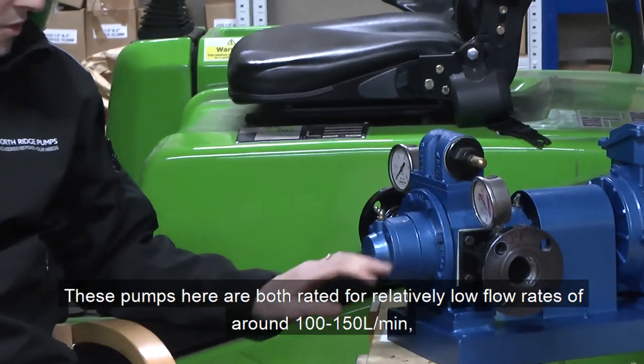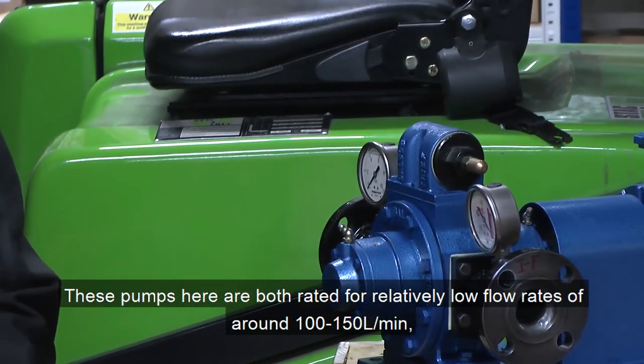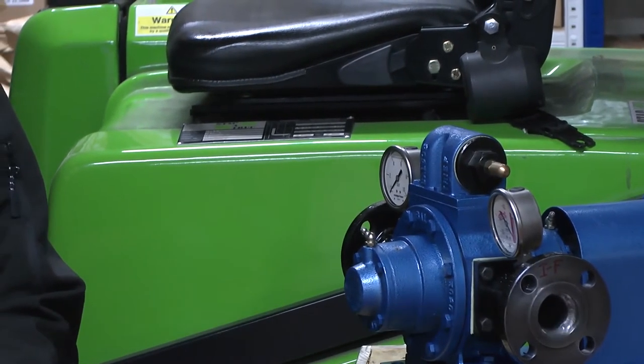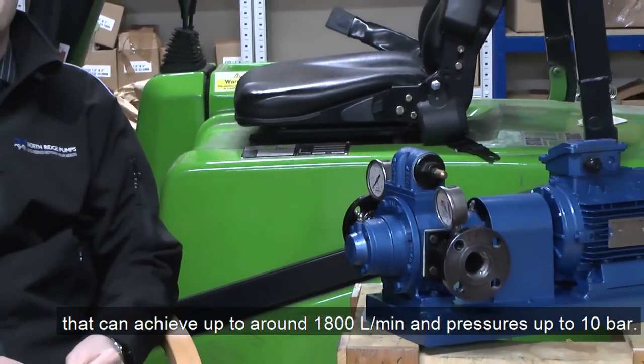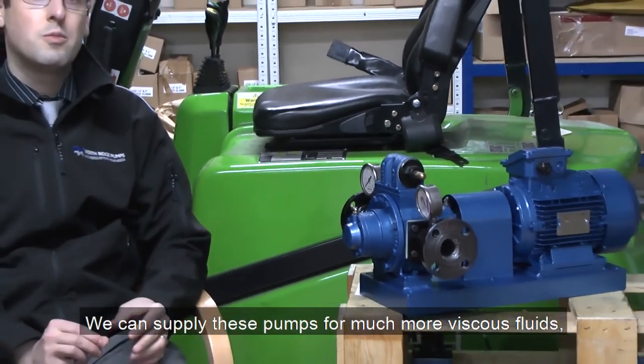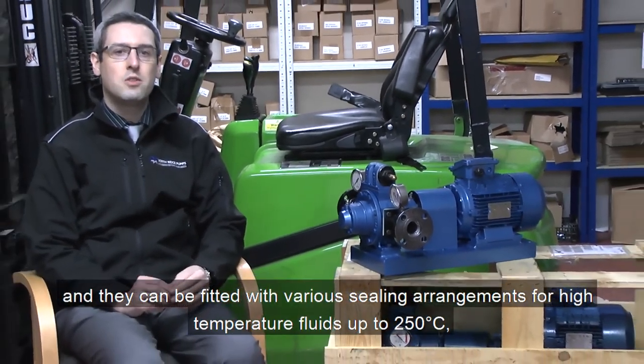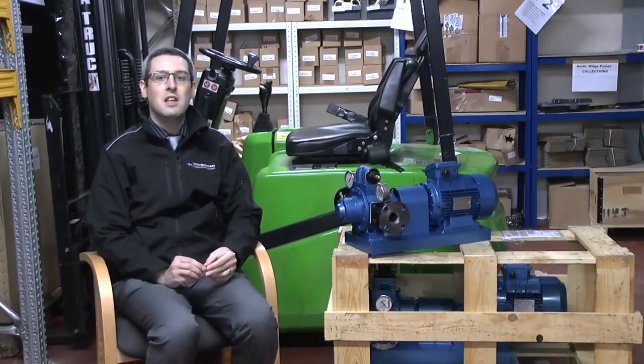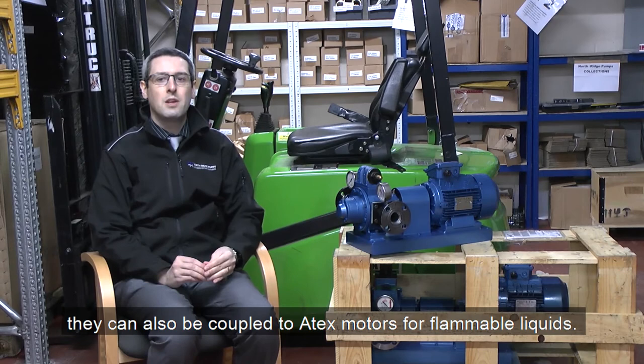These pumps are both rated for a relatively low flow rate of around 100 to 150 litres a minute. However, we do have much larger vane pumps within our range that can go up to 1800 litres a minute with pressures up to 10 bar. We can supply these pumps with much more viscous fluids. They can be fitted with various different sealing arrangements for high temperature fluids up to 250 degrees Celsius. They can also be coupled to ATEX motors for handling flammable liquids.